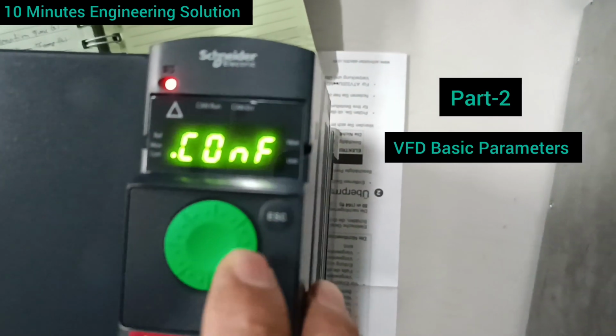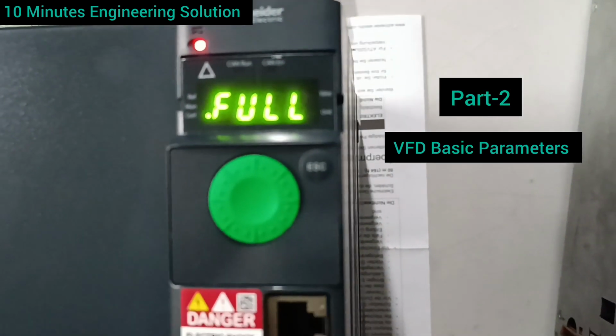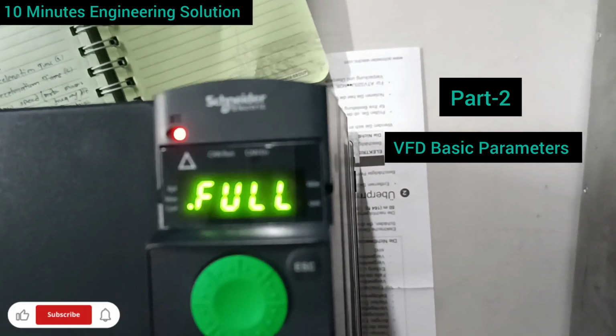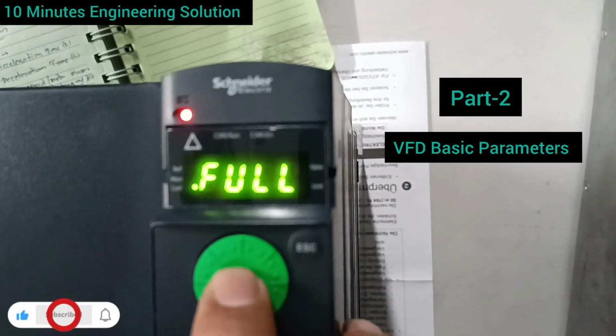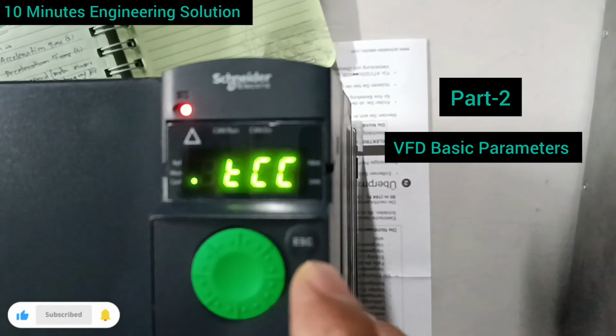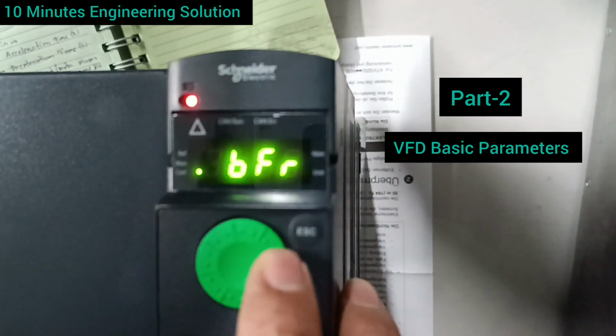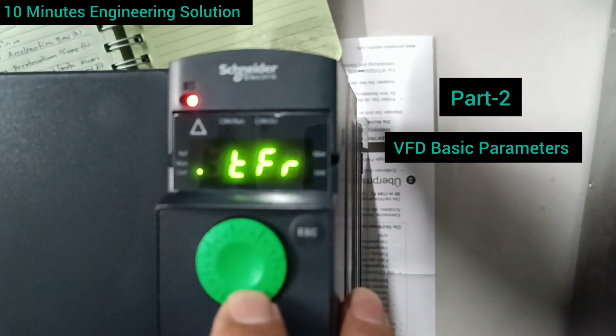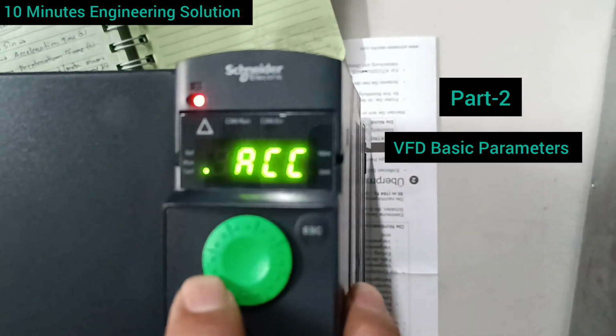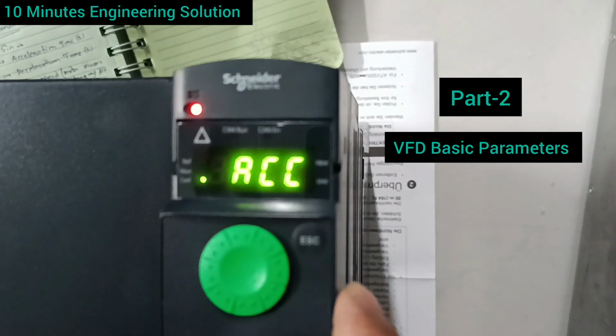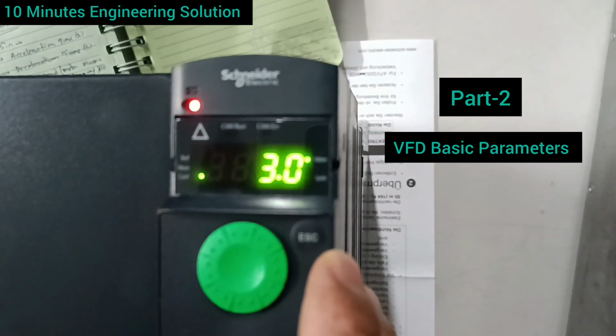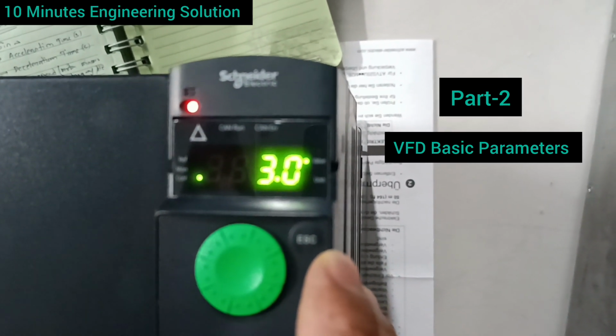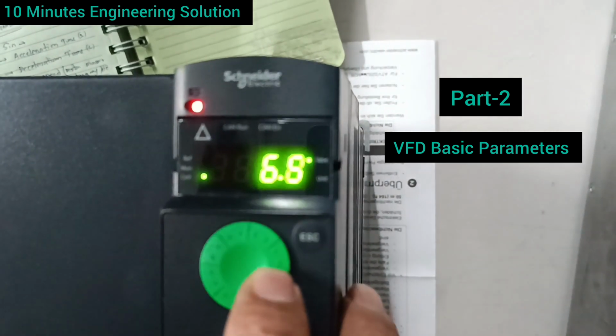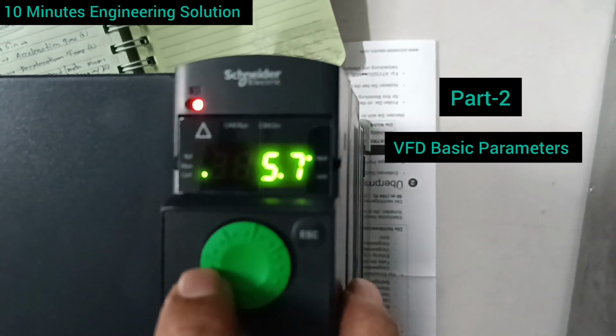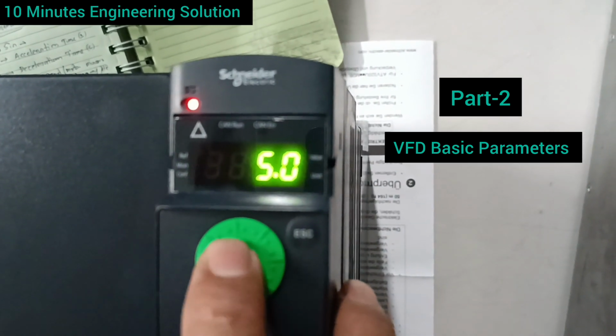Now the VFD basic parameter settings. I'll go to the configurations again and then go to the acceleration time, ACC. This is the ACC, acceleration time setting. The default value is 3.0 seconds, but I have to set this value to 5.0.